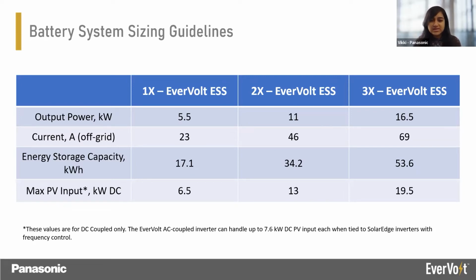And also the maximum PV input for a single system is 6.5 kilowatts of DC power. This is connected across 2 MPPT channels on the Gen 1.5 system. With Gen 2 system, we have 4 MPPTs. Again, I'll talk more about it when we talk about Gen 2. But the best part is, the size of the PV that can be connected to the system also gets multiplied as we stack multiple systems. The PV sizing restriction is again based on how much the battery can handle in case there's an outage and it's fully charged, or if it loses some charge, at what rate it can charge back.